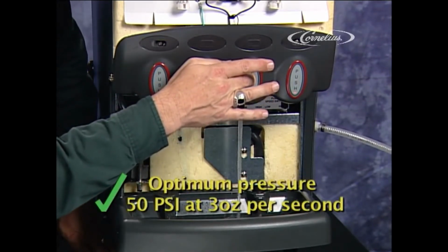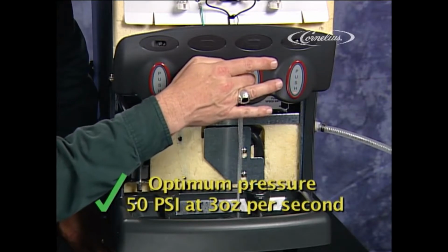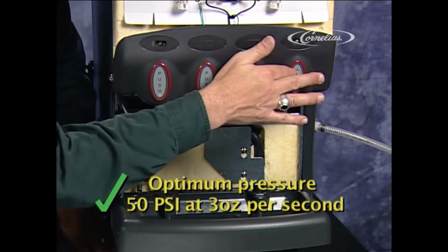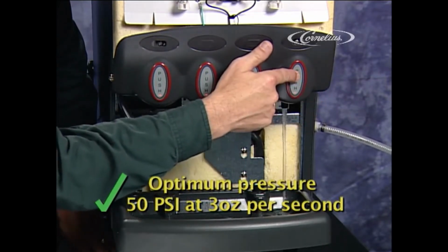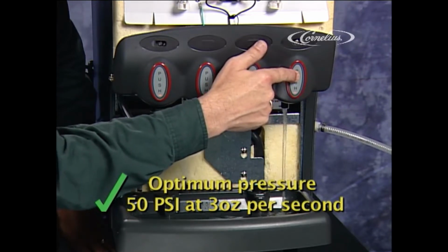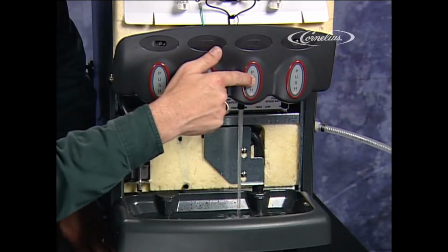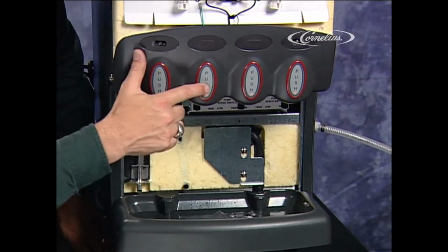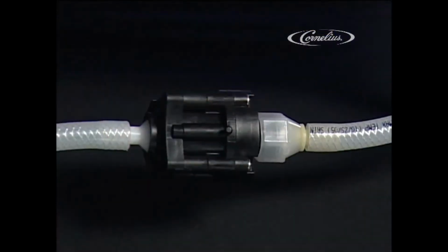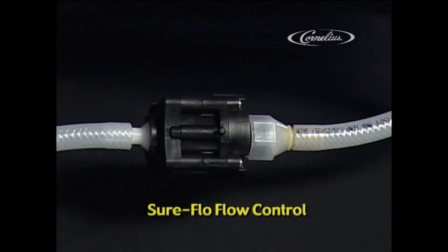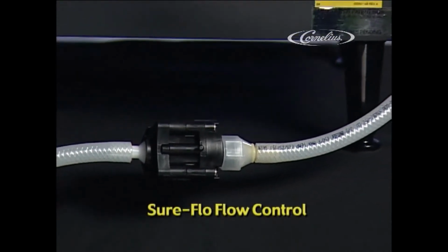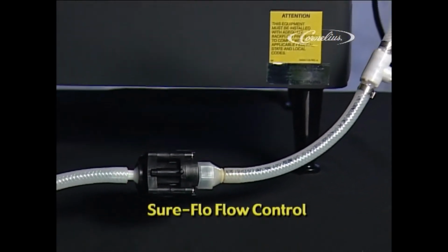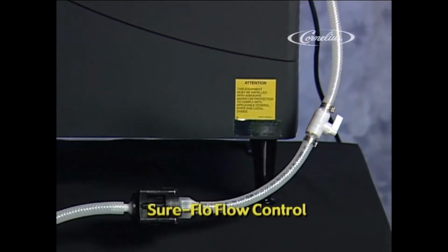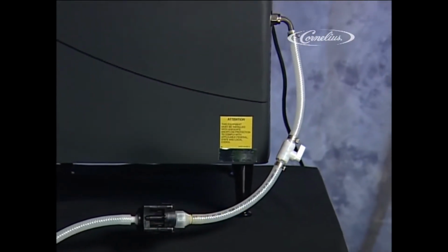Correct and consistent water pressure is very important to the successful operation of this dispenser. The Quest dispenser has an operating range of 30 psi to 80 psi with an optimum pressure of 50 psi flowing at a volume of 3 ounces a second. If you have water pressure issues, especially where you think that the pressure is too high, a SureFlow flow control set at 50 psi is available that can be spliced into this line to allow for good and consistent water flow to the dispenser.